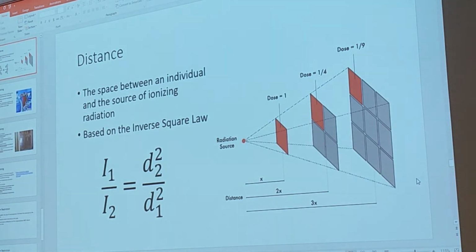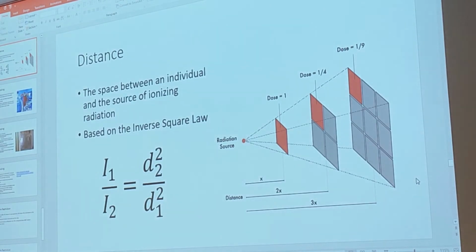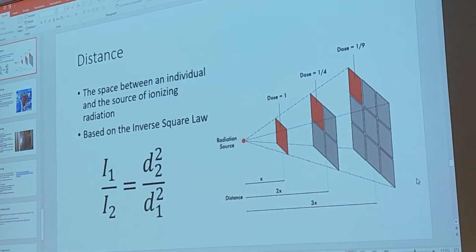Will we be expected to memorize how thick the lead should be for shielding in like secondary barrier? Yes. Good question. So you do need to know the thickness for primary barriers and secondary barriers. Like 1/16? 1/16 for primary. Good. 1/32 too. Good. 1/32 for secondary. Is that 1/16 inches, centimeters, millimeters, feet? Inches. Very good.